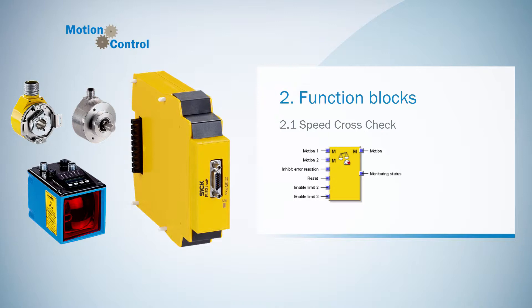This function block generally compares speed values from two different signal sources. The checks made during this process are used to achieve a higher level of safety, in particular if non-safety encoders are used. Sometimes there are temporary or even continuous differences between two measured values — this happens for example by slip, friction, or mechanical behavior. Therefore the function block provides various parameters that can be used to compensate such differences. In this way, wrong switching can be prevented and the availability of the machine safeguarded.